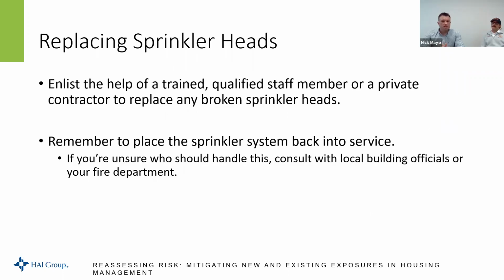So in regards to replacing sprinkler heads, the help of trained, qualified staff members or private contractors can replace any broken sprinkler heads that you may have. Most importantly, remember to place the sprinkler system back in service. There's some NFPA statistics out there that the majority of the time where something goes wrong with a sprinkler system, it's due to the fact that the system was not put back in service properly. Correct. So we can have a fire or an accidental discharge.